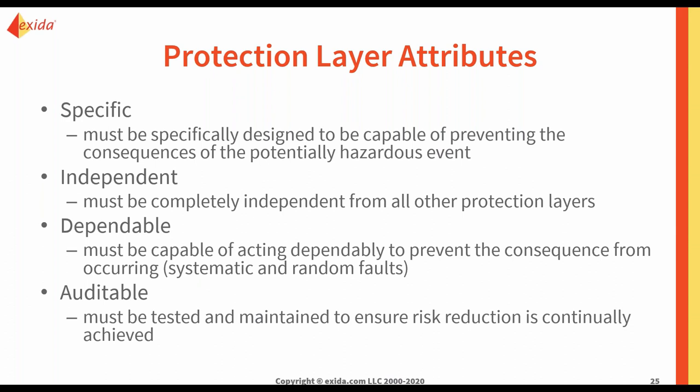And the next criterion is that it has to be dependable, acting dependably to be able to prevent the consequence from occurring. And also it has to be auditable. That means that it can be tested and maintained to make sure that the risk reduction is continually achieved. It's not going to degrade over time because you keep looking at it, keep assessing it to see whether its ability is going to degrade or not.